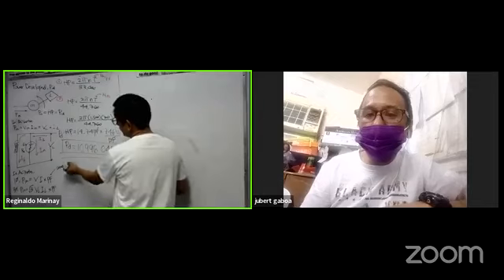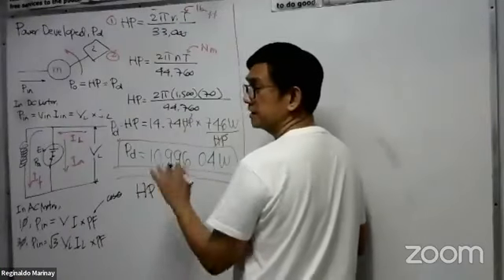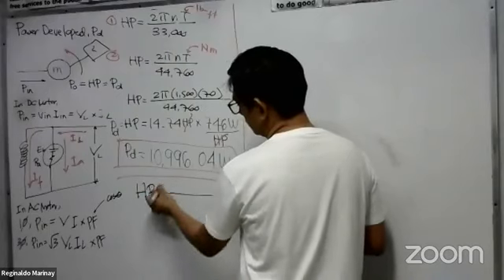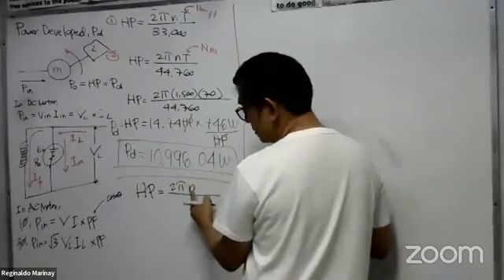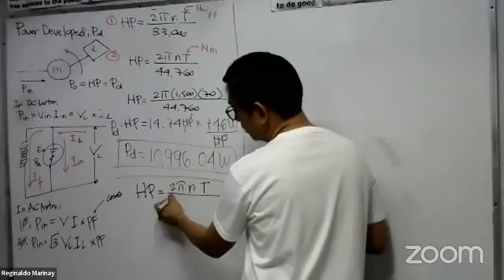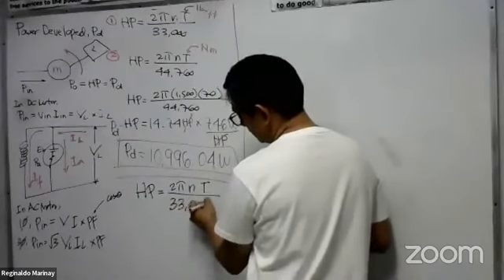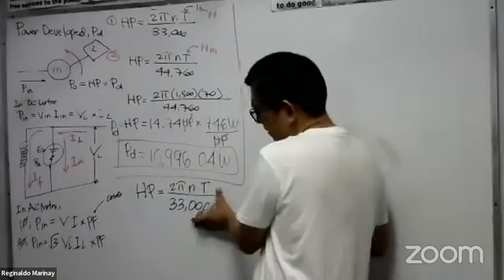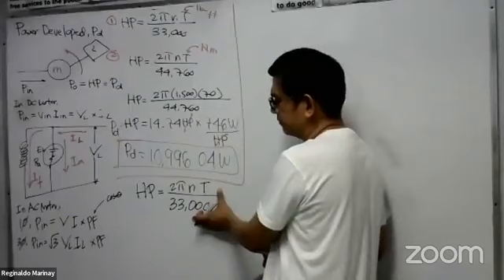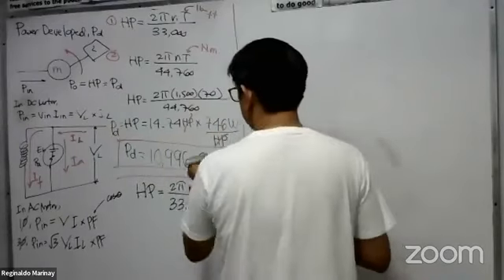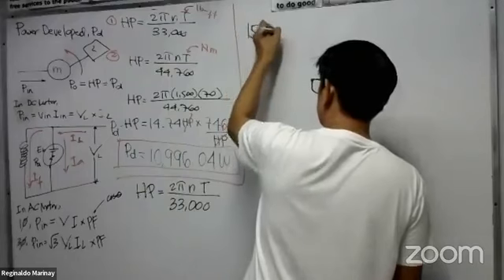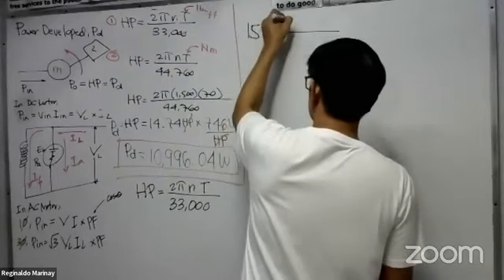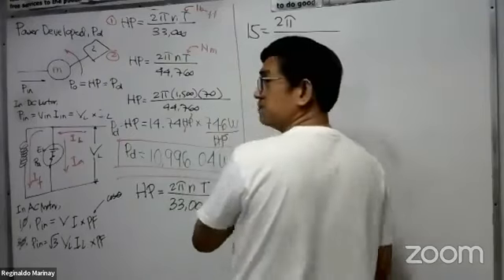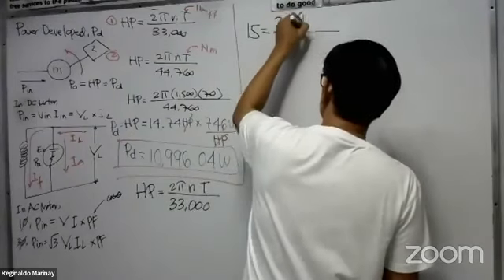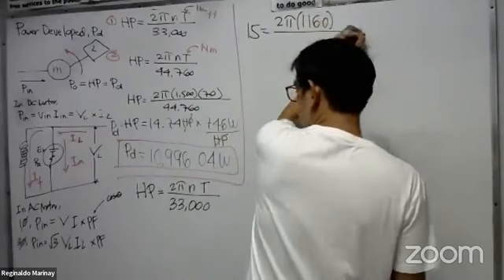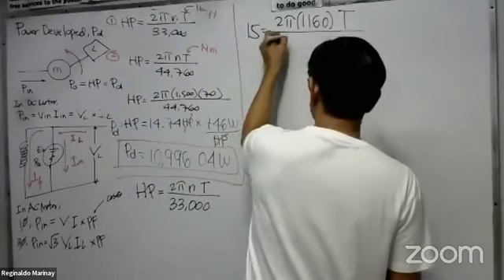I'll give you the formula: horsepower equals 2 pi times the speed times the torque in foot-pound, all over 33,000. That's our English system formula. So we have 15 horsepower equals 2 pi times the speed, 1,160, times the torque, all over 33,000.